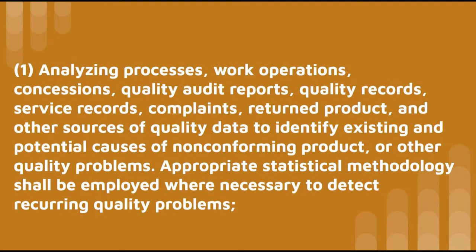And in addition to this, manufacturers need to employ a statistical methodology to detect recurring quality problems. So let's say we have a complaint given a specific issue. Companies need to be able to determine if that's an isolated incident and only that specific device having that issue, or if this is a widespread issue with their device, so then they can address it.